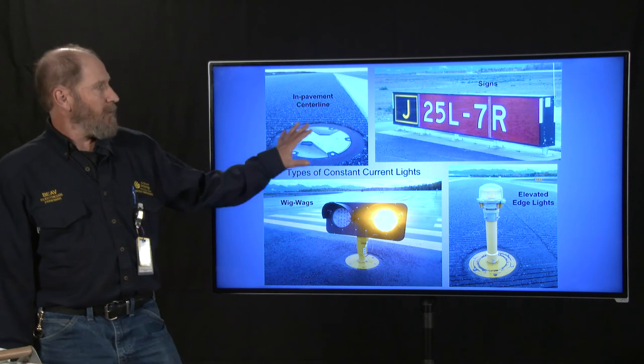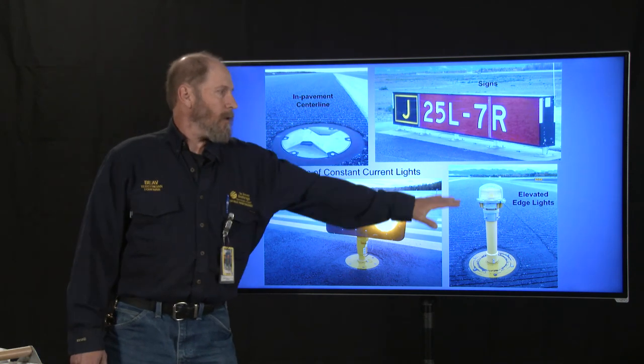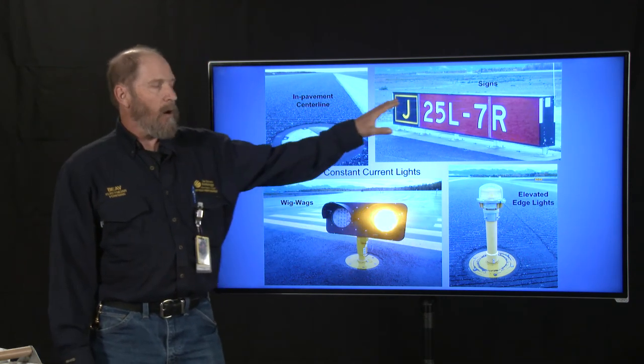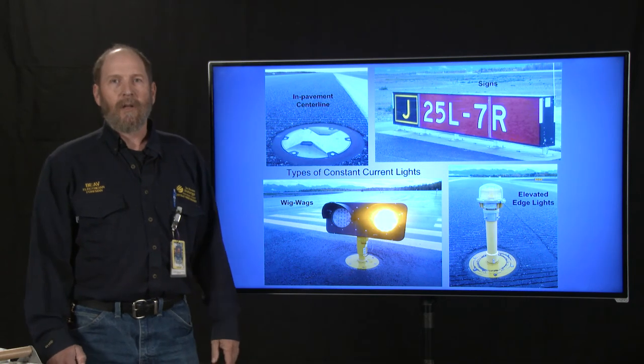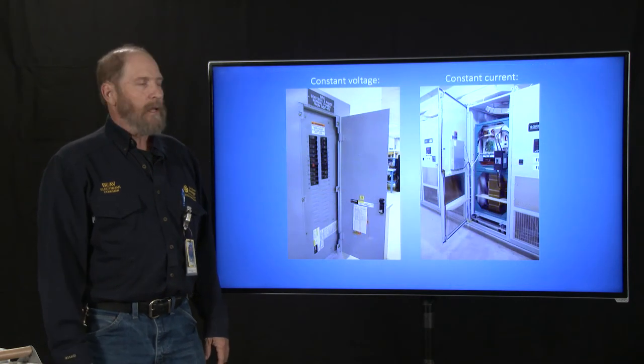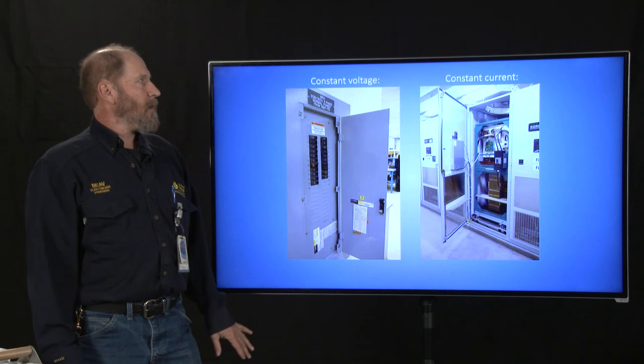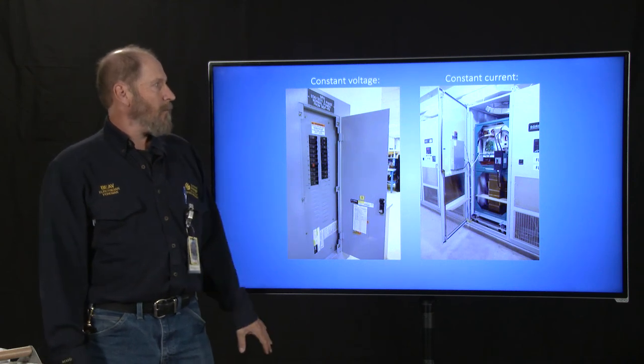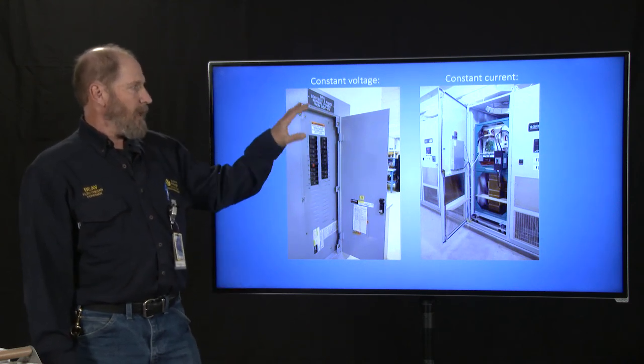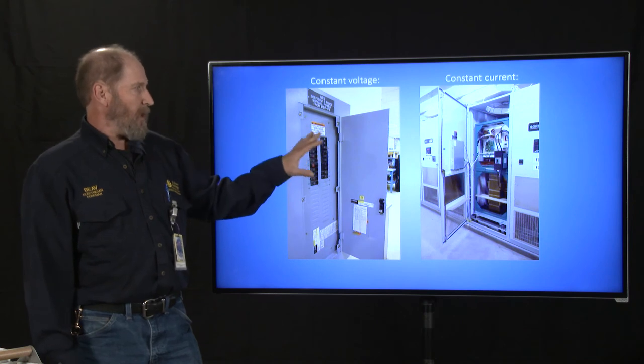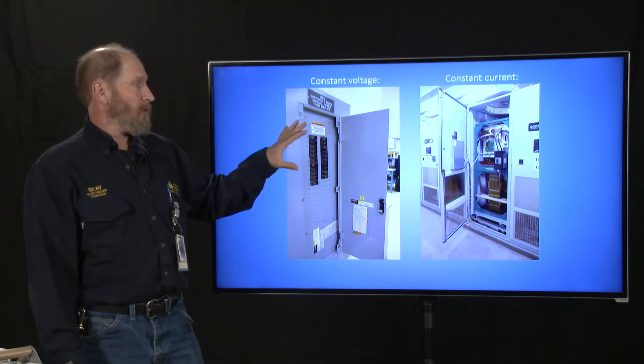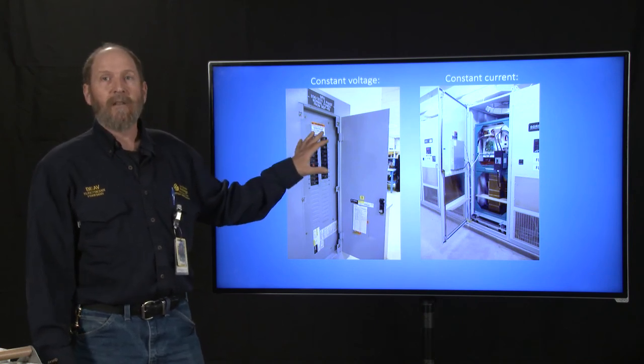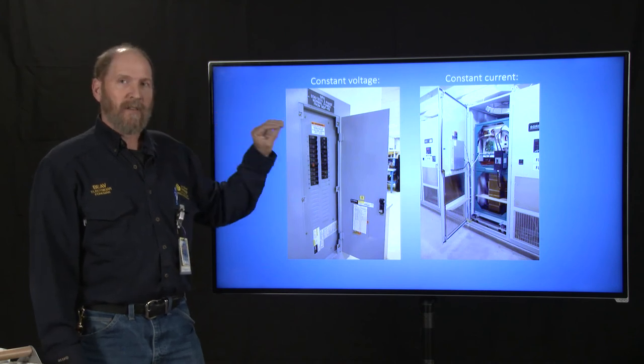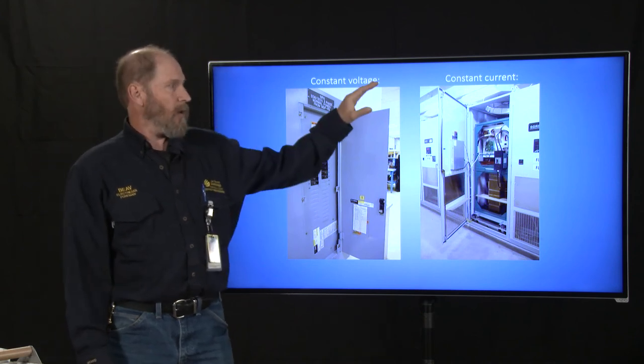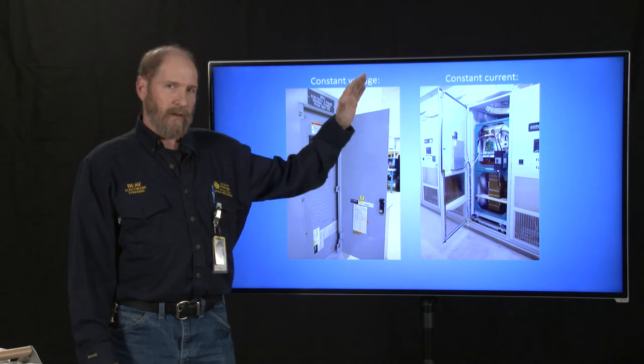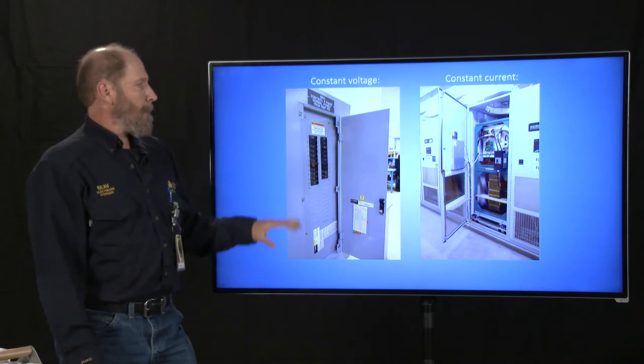So all of these different lights are on a runway. All of them run off of a constant current lighting system. So the difference is between constant voltage and constant current. Constant voltage is just like it sounds. It'll be like 120 volts, 208 volts, 480 volts. The voltage stays steady. Constant current, the current stays steady and the voltage goes up and down.